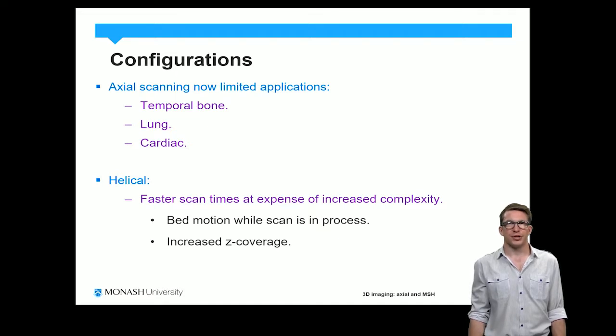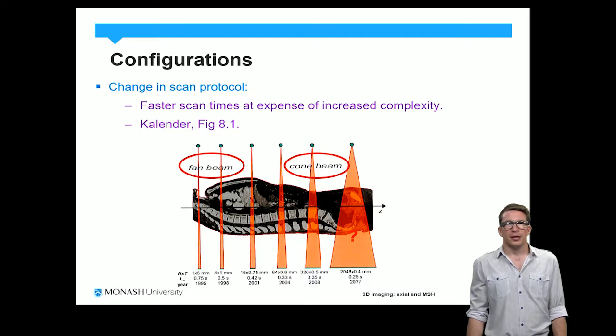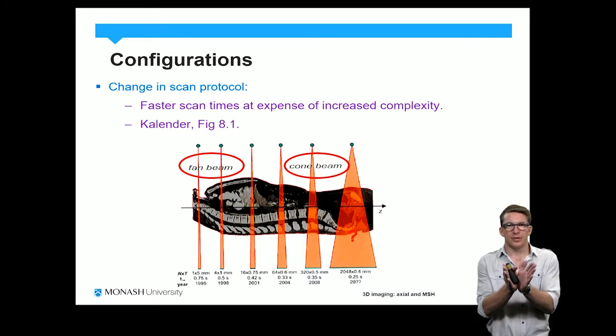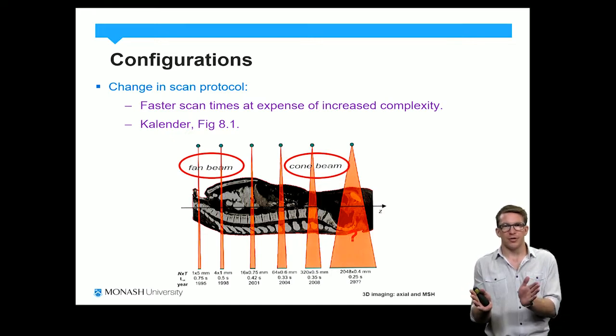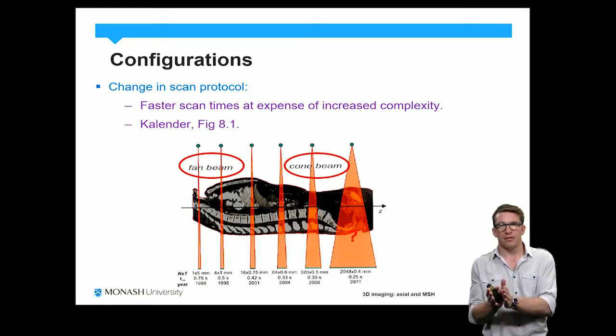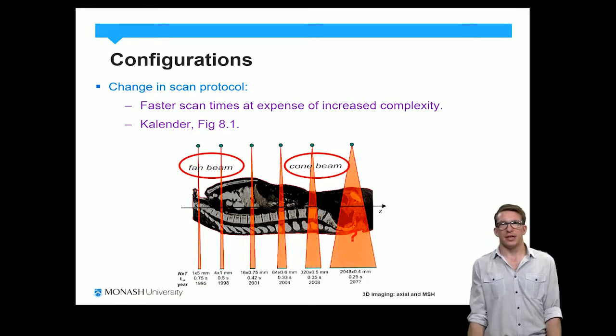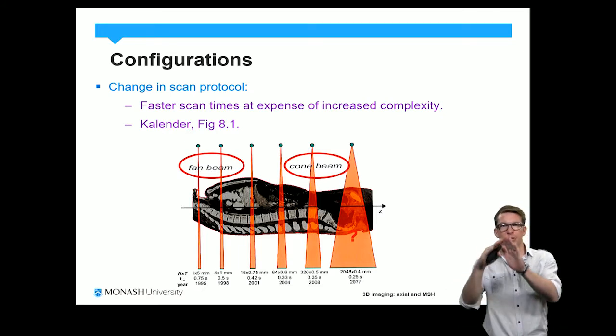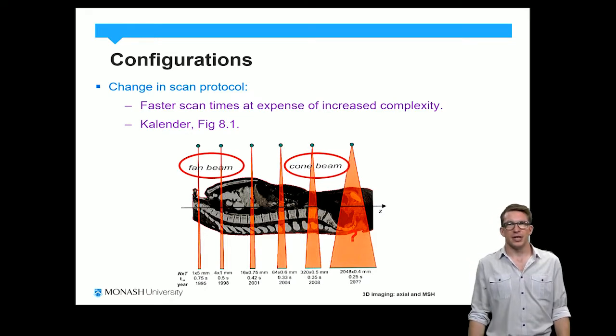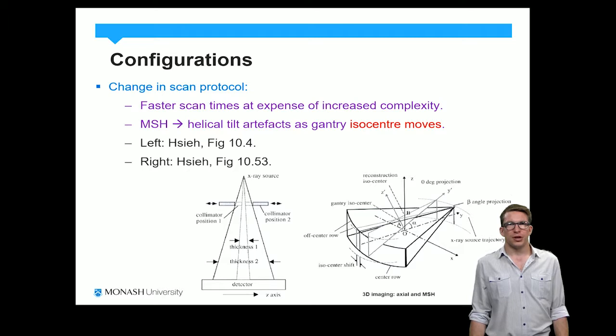The moving bed gives us increased Z coverage. As we've gone from single-slice helical to multi-slice helical and expanded out the divergence of the beam in the Z axis, we've moved more and more towards cone beam CT. Cone beam CT is very much the extreme of helical scanning. However, there is a further significant difference in that the detector used is typically a flat panel detector in cone beam CT, rather than the arc detector used in helical scanning. As we've moved to multi-slice helical scanning, some of the reconstruction issues have become more complicated.